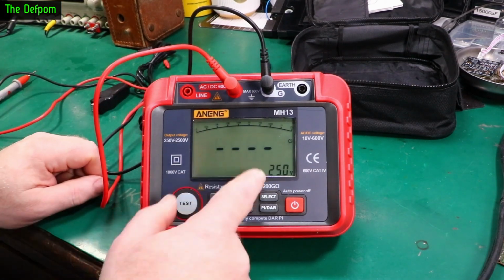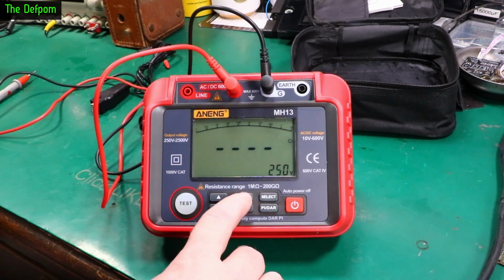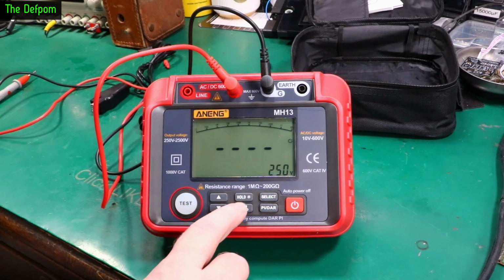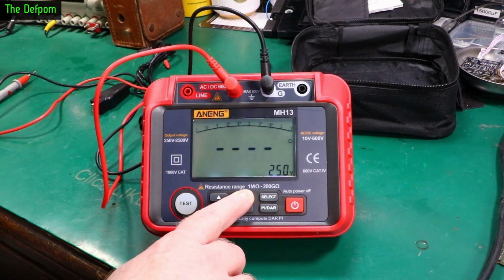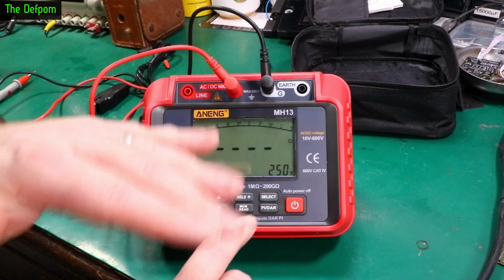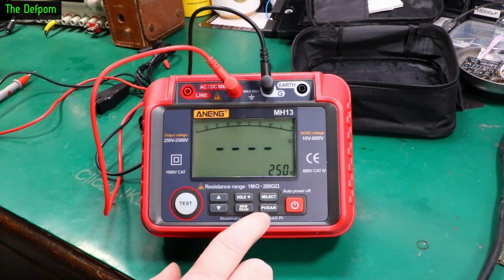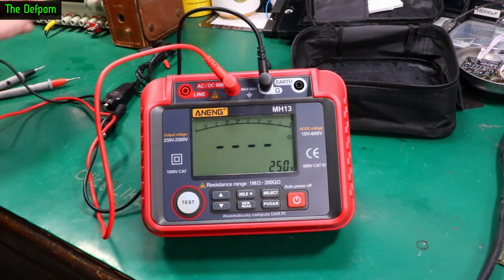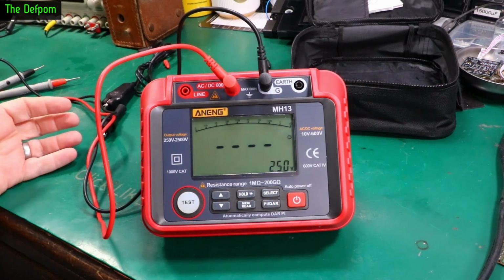The next selection is going back to insulation resistance testing again. So we've got hold here, which holds a reading, and you hold it down, backlight turns on. You can't see it too well with my lighting here, but you'll probably be fine. When in situations where you need a backlight, you're probably looking just fine. PI and DAR. Let's change this setup to be insulation resistance testing.